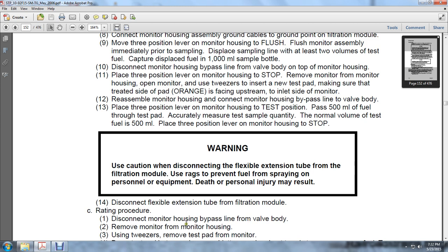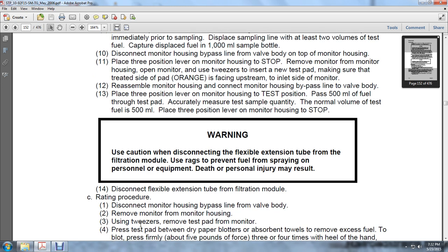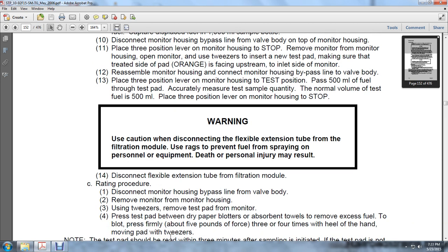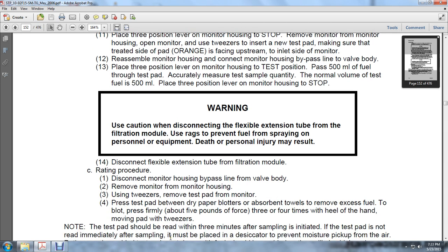Remove the monitor from the monitor housing. Use tweezers. Remove the test pad from the monitor. Press the test pad between the dry blotters and absorbent towels to remove the excess fuel. Apply firm pressure, about 5 pounds of force, 3 to 4 times with the heel of the hand. Remove the pad with the tweezers.